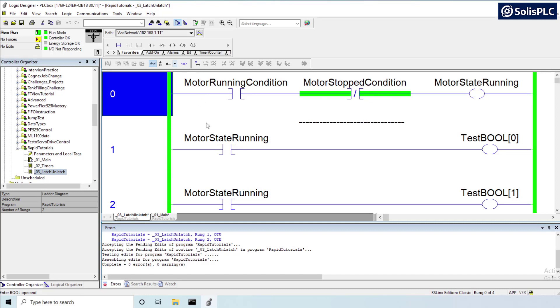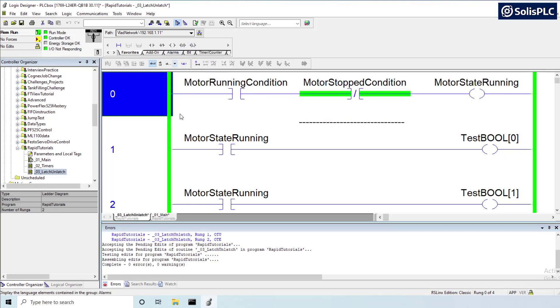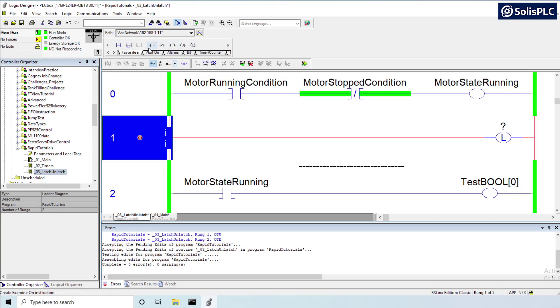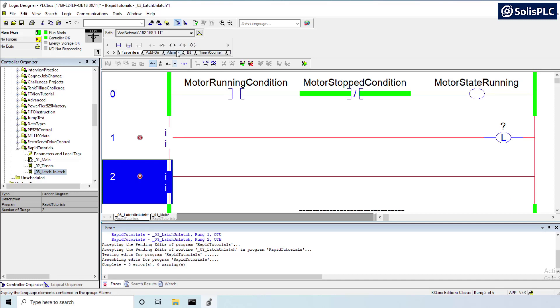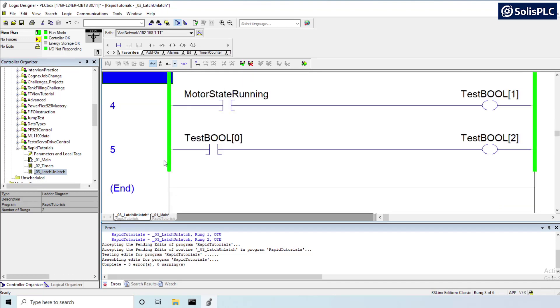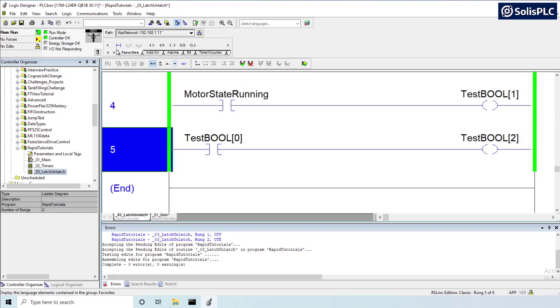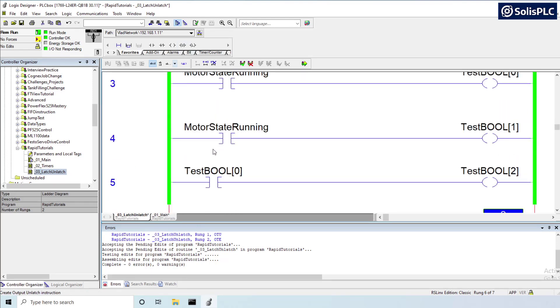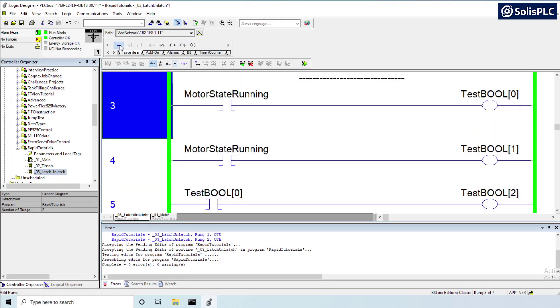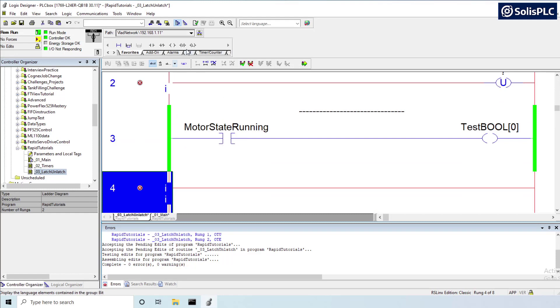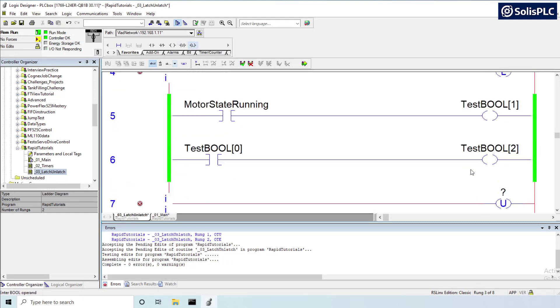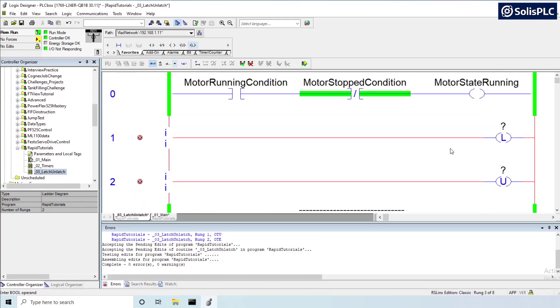Now the last thing I want to mention is that with latches and unlatches you can use them in multiple locations and that's again something I would never recommend. So if you do use latch and unlatch as I've said multiple times, if you use latch then you have another rung that unlatches, put all of your logic under the unlatch bit that is currently in this rung. Don't start creating for example three rungs below, there's going to be another rung with unlatch, then somebody else is going to come in, add a rung in the middle here that's going to for example latch this. This becomes extremely complex to troubleshoot. In any case that's all I have for you today and I'll see you next time.